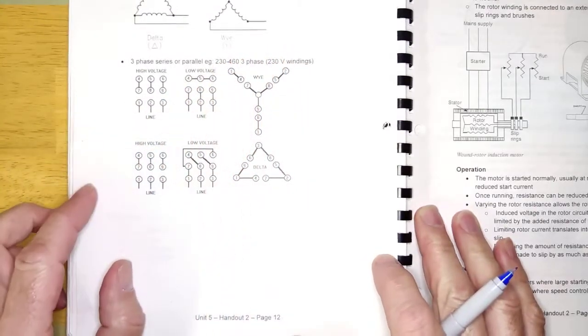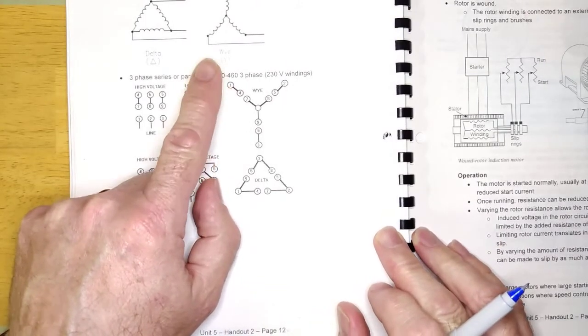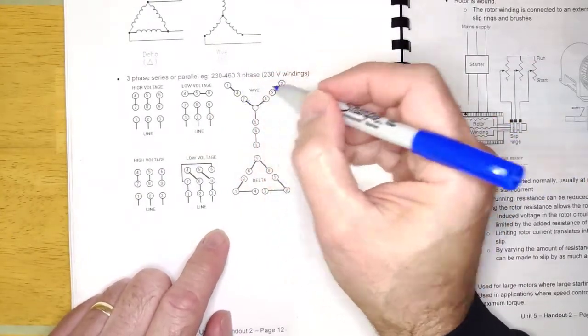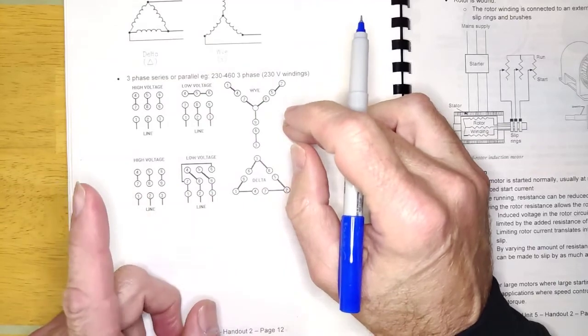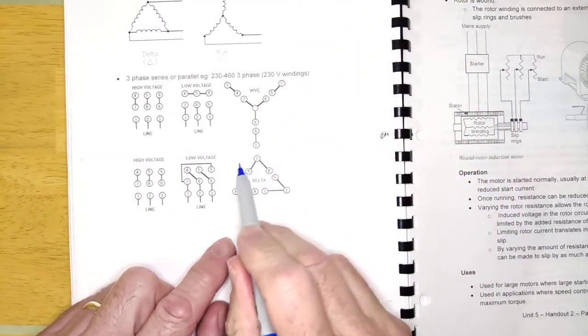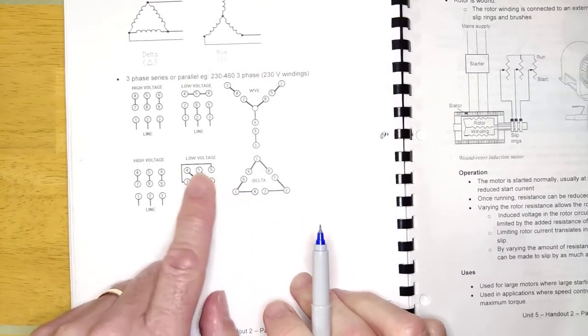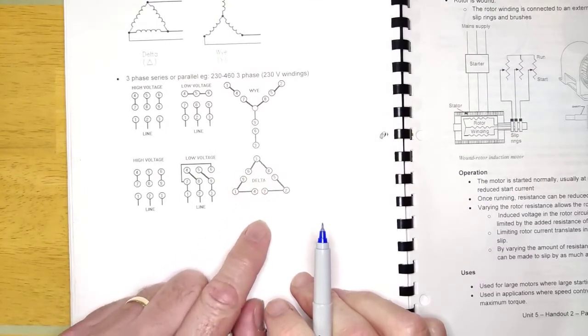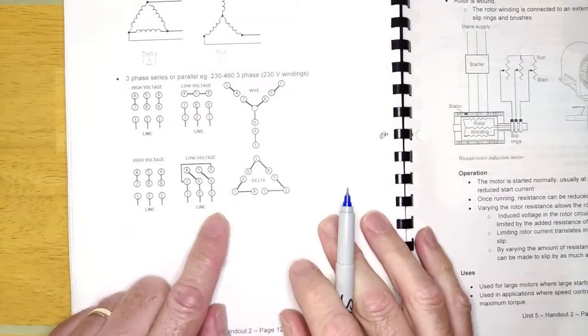So a lot of motors, this is single phase, but three phase does it the same way. A lot of motors, when they are rated for dual voltage, meaning that you can connect them to two different voltages, it will basically be wiring the thing up in series or parallel, depending on whether you're connecting at high voltage or low.